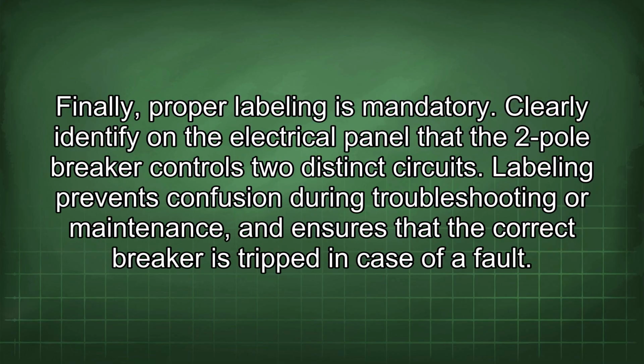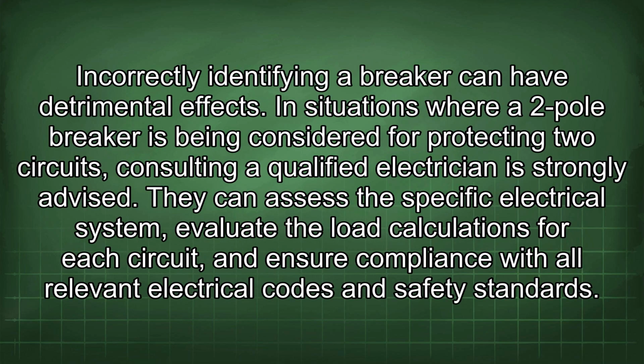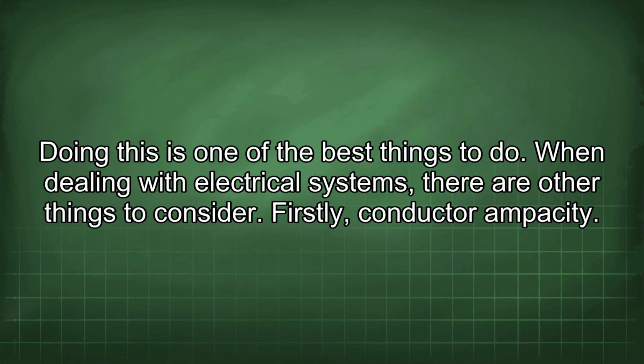Finally, proper labeling is mandatory. Clearly identify in the electrical panel that the two-pole breaker controls two distinct circuits. Labeling prevents confusion during troubleshooting or maintenance and ensures that the correct breaker is tripped in case of a fault. Incorrectly identifying a breaker can have detrimental effects. In situations where a two-pole breaker is being considered for protecting two circuits, consulting a qualified electrician is strongly advised. They can assess the specific electrical system, evaluate the load calculations for each circuit, and ensure compliance with all relevant electrical codes and safety standards. Doing this is one of the best things to do.